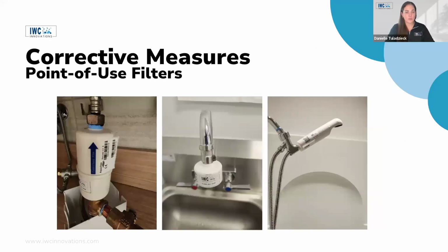So what happens if poorly controlled levels of Legionella are detected in your system? 0.2 micron point of use filters are a great short-term control measure. They're installed right at the faucets and shower heads to physically block bacteria from passing through. These filters are especially valuable in hospitals, nursing homes, and facilities during outbreak investigations to protect vulnerable individuals and prevent additional exposures. While they don't solve the root problem in the plumbing system, they buy time to address the bigger issue and provide peace of mind, knowing there's a barrier between the contaminated water and the people using the sinks and showers.